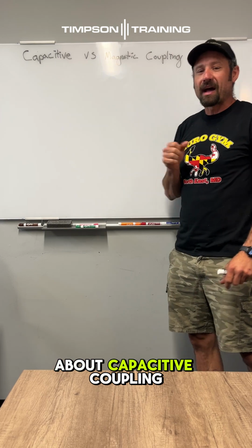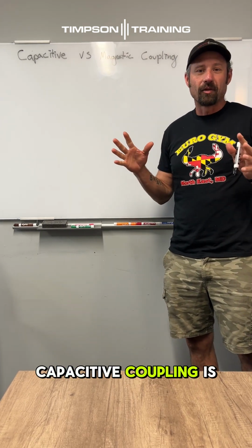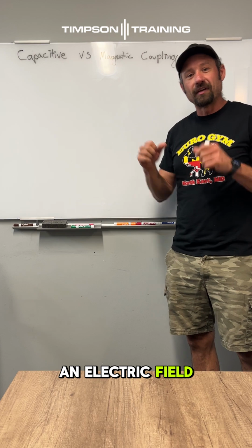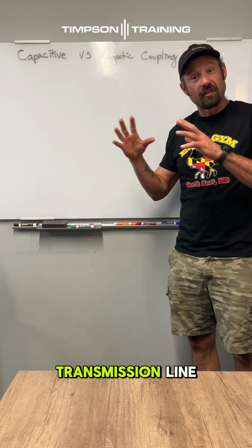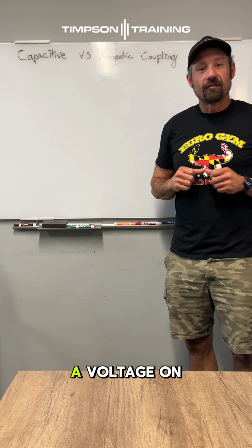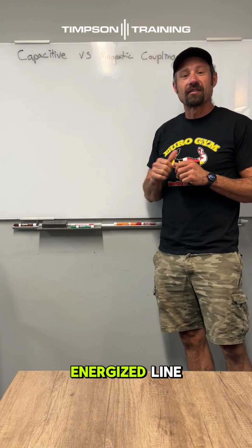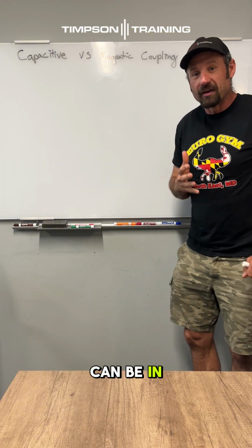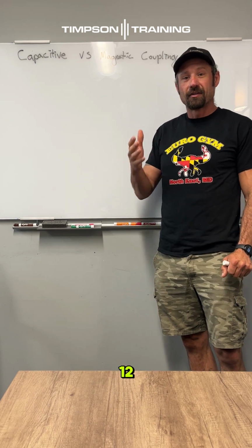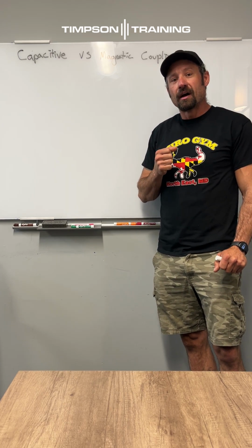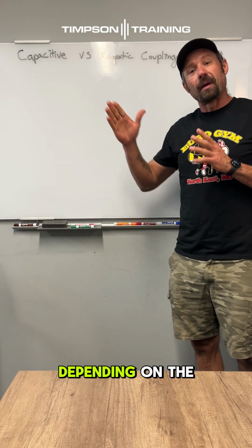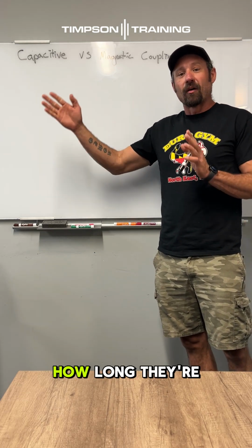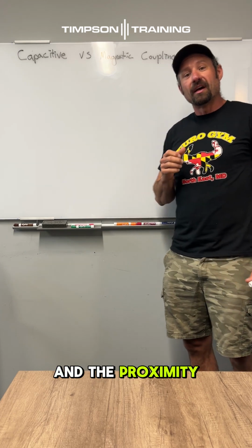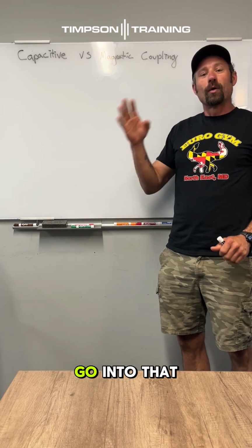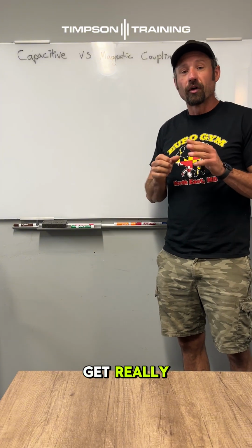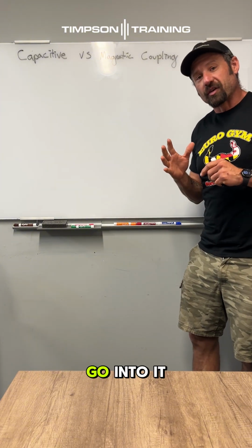So we'll talk about capacitive coupling first. Capacitive coupling is when we have an electric field on an adjacent transmission line that induces a voltage on a de-energized line, and that voltage can be in the tune of 1200, 1300, 1400 volts, even higher depending on the length of wire, how long they're running together, and the proximity. We're not going to go into that calculation because it can get really difficult, there's a lot of variables involved.